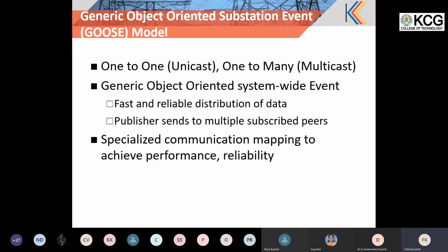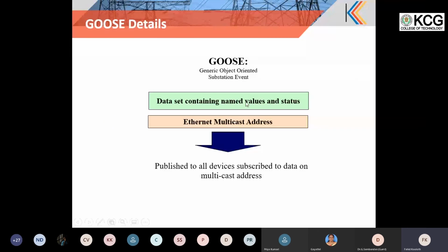But the reliability, as sir was asking, the reliability mechanism of GOOSE is retransmission with a variable retransmission interval. That is the only mechanism to ensure reliability, because we are not taking any feedback whether it is delivered or not. So that is one of the keys. So the GOOSE element is there, then a data set containing all the values. Based upon the trigger condition, a snapshot is taken, and then this is directly embedded onto the Ethernet and published over the Ethernet to all the subscribers in the network.